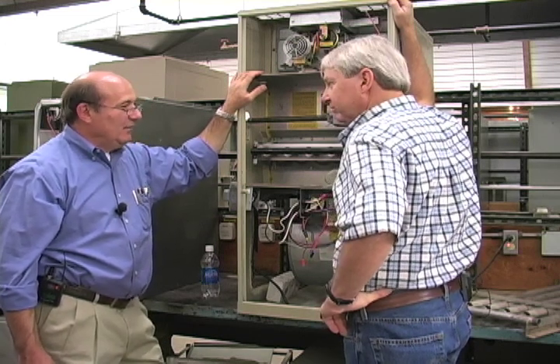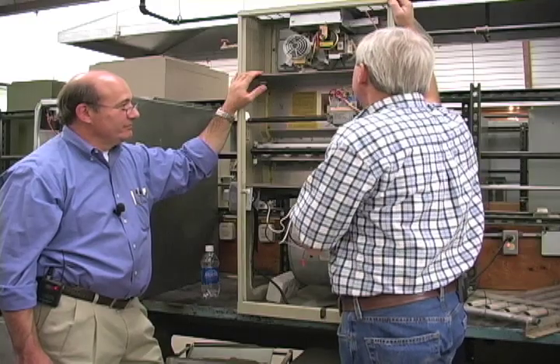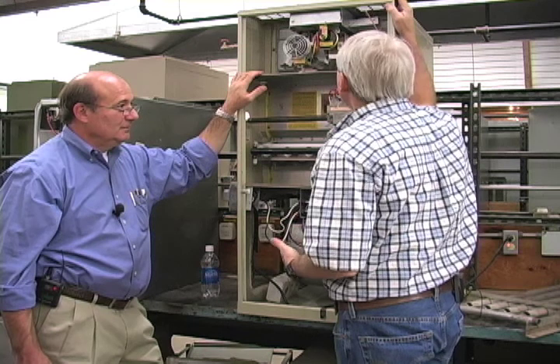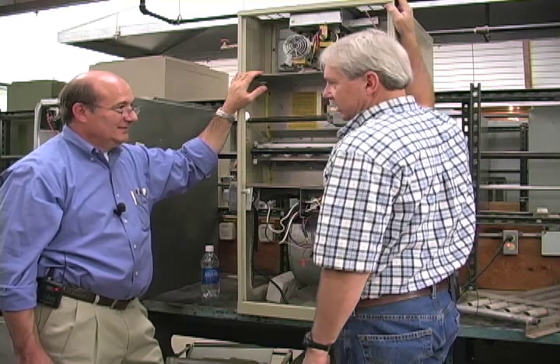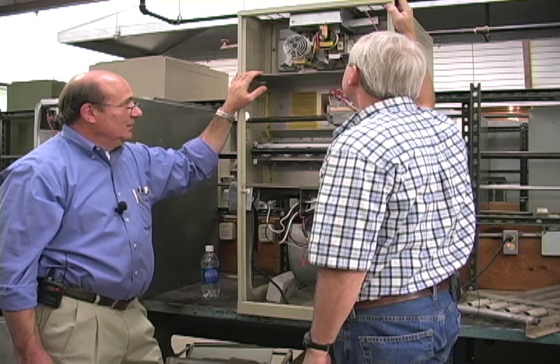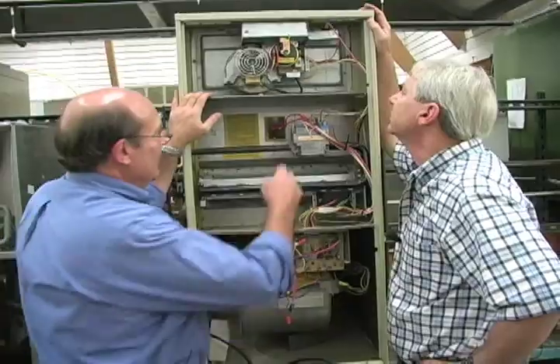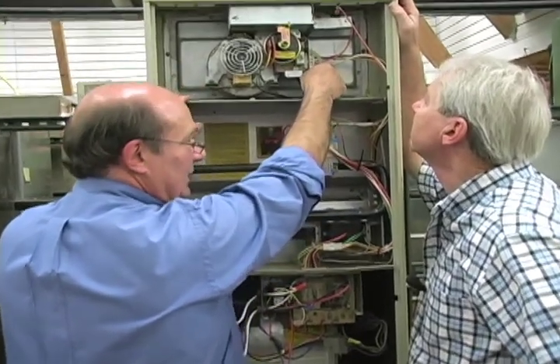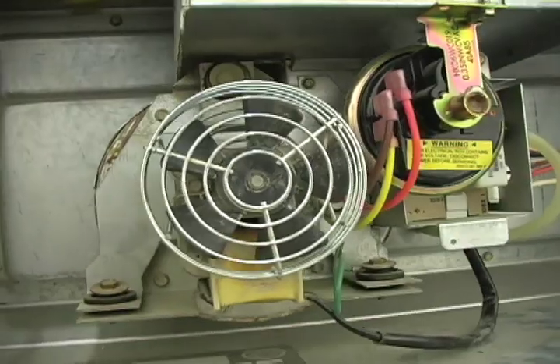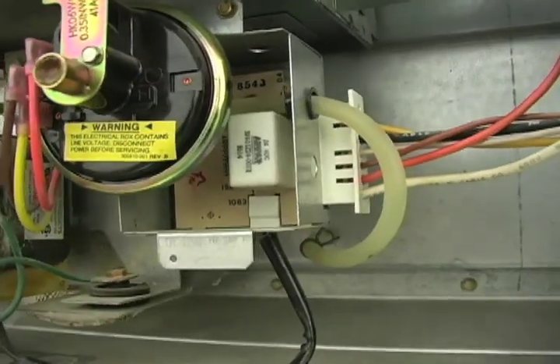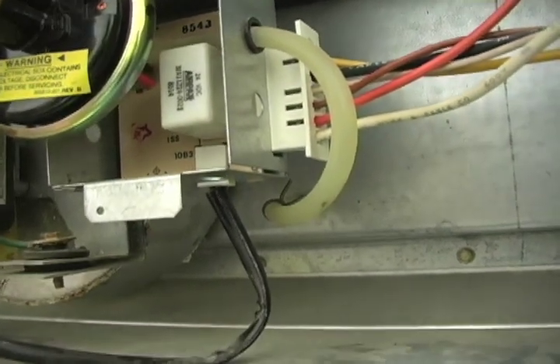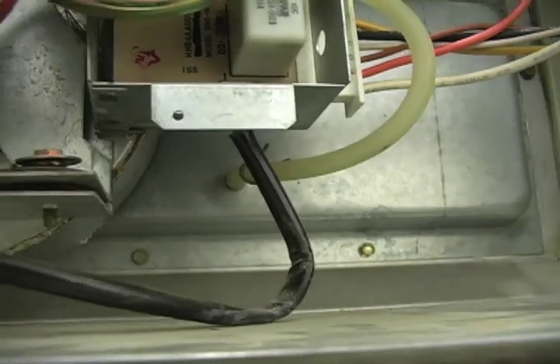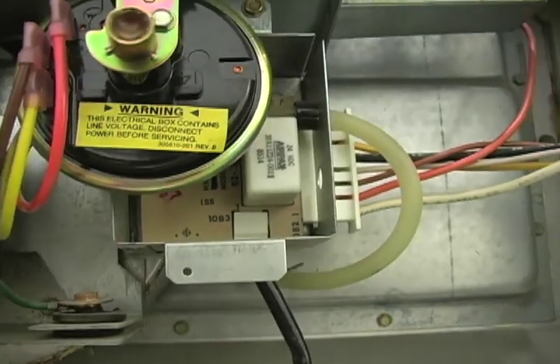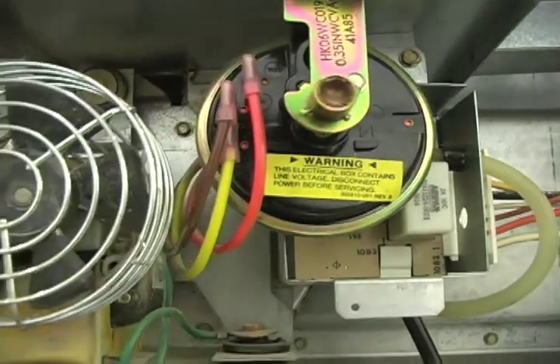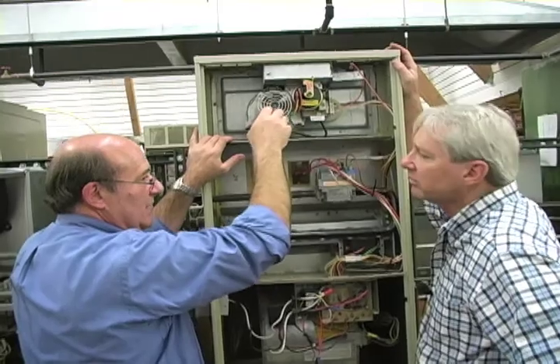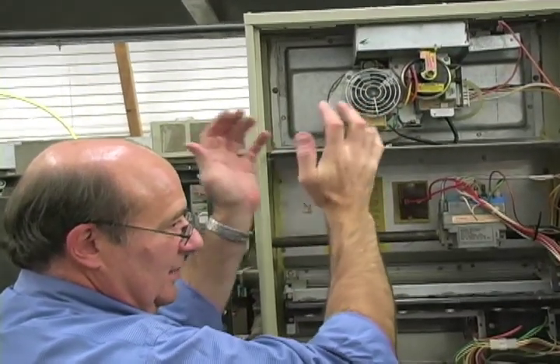That's, I think, the basic rundown on your 85% furnace, then, Ken. And that's about the same whether it's induced or forced. Forced. Yeah. Control sequences are all the same. The only difference in the actual operation is that this pressure switch, instead of detecting negative pressure in the heat exchanger, would be detecting positive pressure in the heat exchanger. Some of the older systems years ago too, certainly on the rooftop units and the light commercial stuff, rather than a pressure switch on those combustion chambers, used what we call a centrifugal switch on the inducer motor itself. As that motor started spinning up, it would throw these counterweights out and close the switch on the outside.